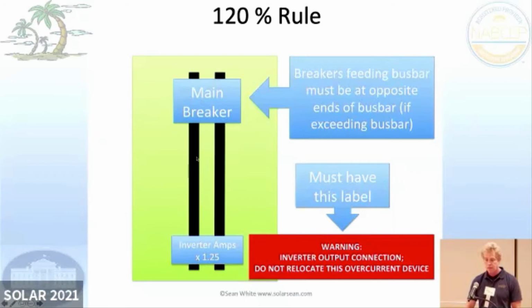So we take the bus bar. Let's just do a calculation. Bus bar, 100 amps, 100 times 1.2, 120 amps. You've got a 120 amp allowance. And let's say we had a 100 amp main breaker. That leaves us with 20 amps for the solar.